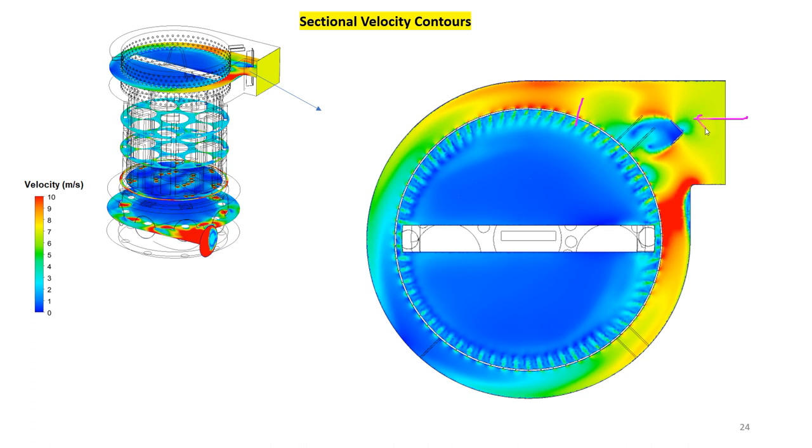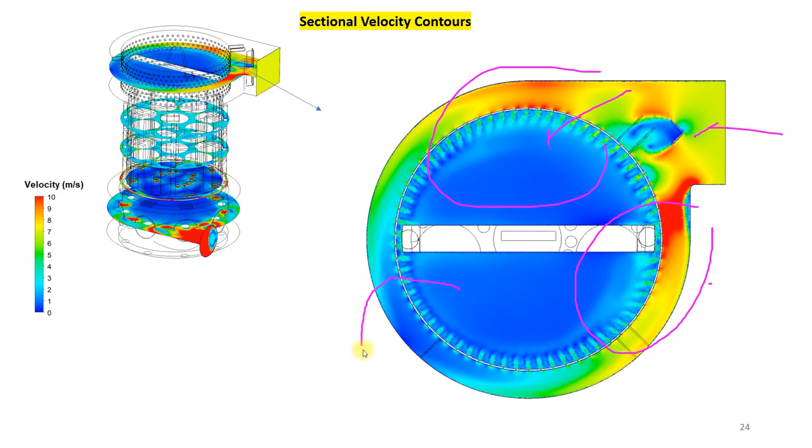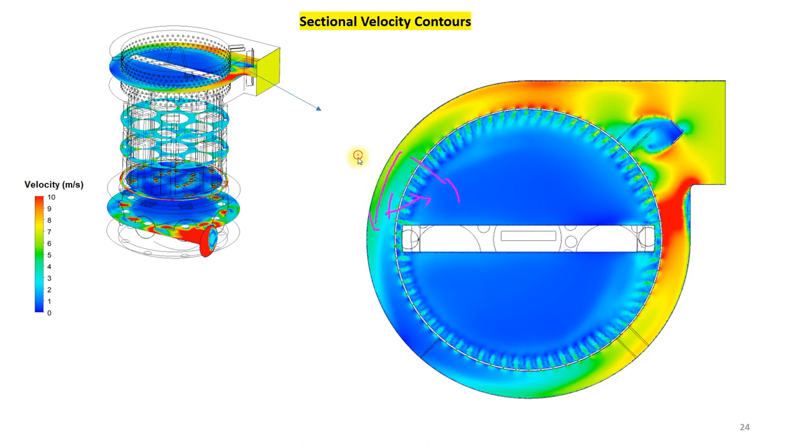For the cross section at the top section, fluid flows properly on the perforated plate. This perforated plate tries to distribute velocity more uniformly, but here most of the air flows through those sections near the inlet, because most air tries to flow to this section. Because those holes are away from the outlet, here velocity is less. Because most of the fluid already passes through this hole, its mass flow rate comes down when it flows around the circumference.